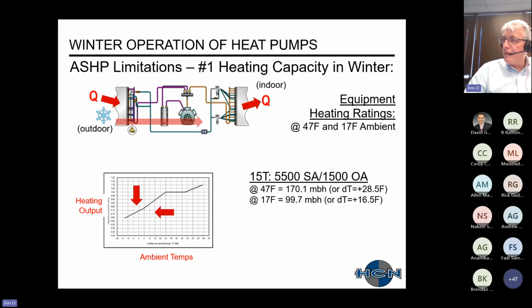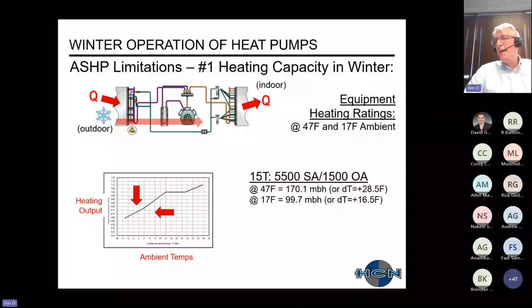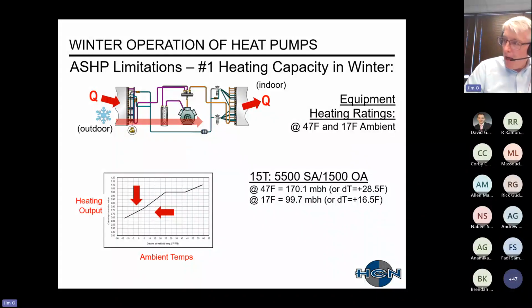And then just back to my 15-ton example with these airflows. At 47 degrees, I'm getting 170 MBH, or temperature rise of about 28 degrees. But if it's 17 degrees out, I'm getting 100 MBH, which is about a 40% reduction. So just keep that in mind when you're designing for your heating system. You'll design for that 17 or 10, or once again, Philadelphia's design temperature is 9 or 10 degrees ambient. A lot of engineers want a safety factor, so in our territory, some people will use 0.